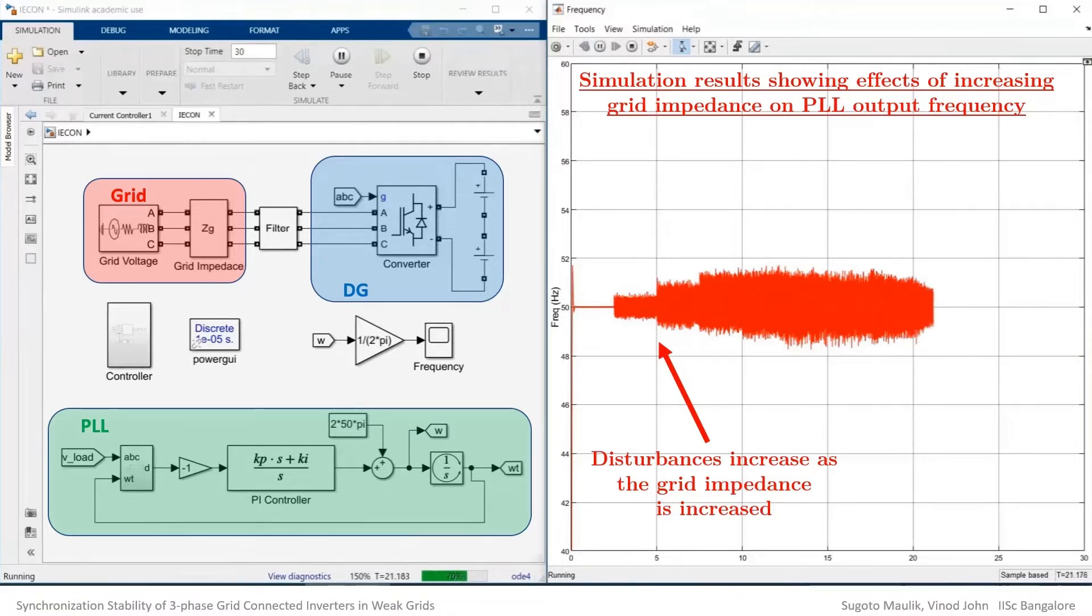Beyond a certain value of grid impedance, the PLL can be seen to lose stability and desynchronize from the grid.